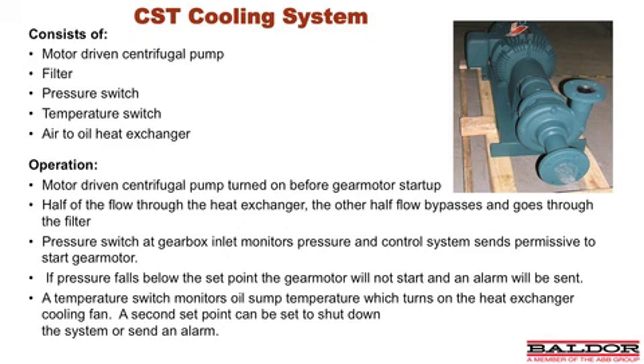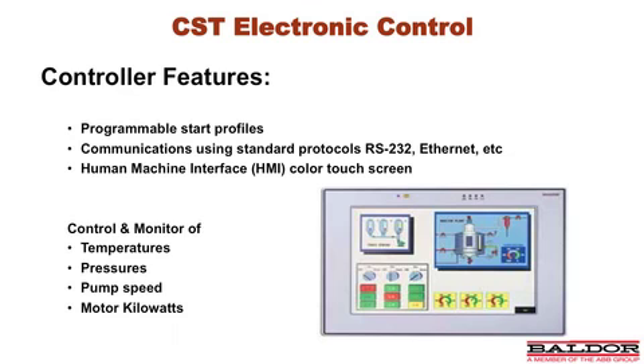The pressure switch at the gearbox inlet monitors pressure and controls the system permissive to start the gear motor. If pressure falls below the set point at the gear motor, it will not start and an alarm will be sent. A temperature switch monitors oil sump temperature, which turns on the heat exchanger cooling fan. A second set point can be set to shut down the system or send an alarm, depending on what is happening within the system. The electronic controller has programmable start profiles. It communicates using standard protocols of RS-232, Ethernet, and other methodologies. You also have a human interface using a color touchscreen. The controller monitors temperatures, pressures, pump speed, and motor kilowatts.